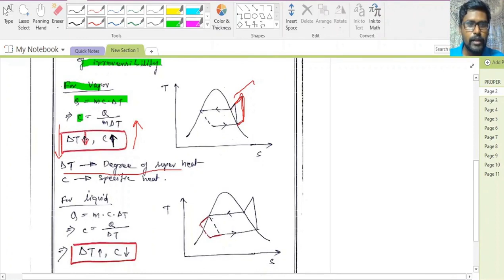Similarly for liquids, Q is equal to m c delta T. Then similarly specific heat C is equal to Q by m delta T. That means if you decrease the specific heat, then what will happen? Then the degree of subcooling will increase. If you see the diagram here, this is the cycle without subcooling. So what is the refrigerating effect we are getting here? This is the refrigerating effect.